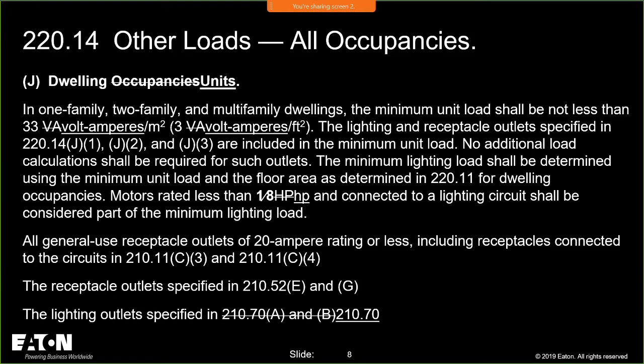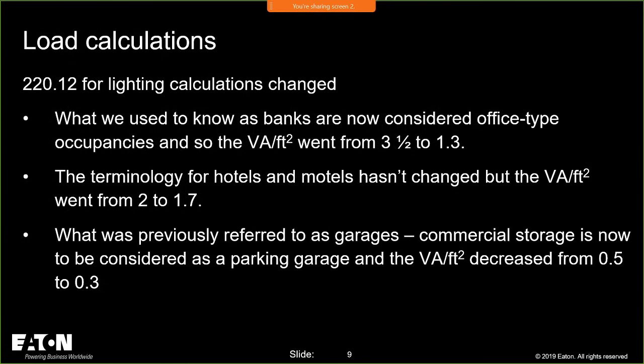And then you'll notice we have the lighting outlet specified in 210.70. We didn't specifically call out A and B. So that was some minor changes there. But we didn't really change anything on the dwelling unit side. We just relocated, we pulled things out of the table and put them over to 220.14J.